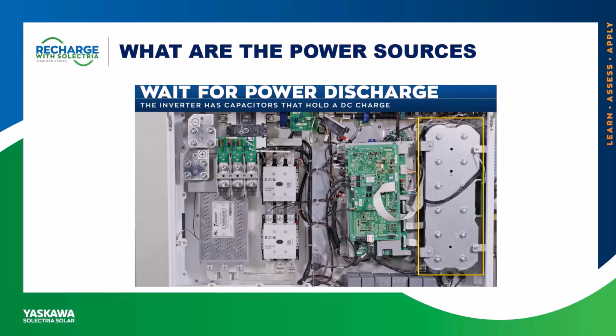On the right there's a big old bank of capacitors that'll hold a charge for several minutes. It says 5 minutes because that's typical, since there's a little discharge board there. I don't think this is unusual for people familiar with the field, but keep that in mind - don't just immediately open things up and start working on them. We got to verify the voltage is not present.